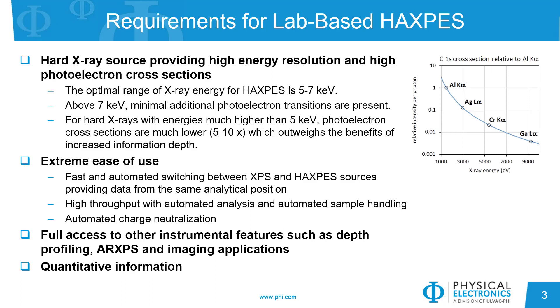HAXPES is not new and has been performed at synchrotrons for many years. These light sources have the advantage of tunable photon energies and very high flux, but there are several drawbacks. Time on a beamline is competitive and requires a lot of preparation for a successful experiment. Charge neutralization and quantification are also difficult, limiting the types of experiments a user can perform. Therefore, a lab-based HAXPES instrument can provide users a more accessible system that is easy to use and highly automated, with features commonly found in current XPS instruments such as charge neutralization, imaging, and depth profiling.